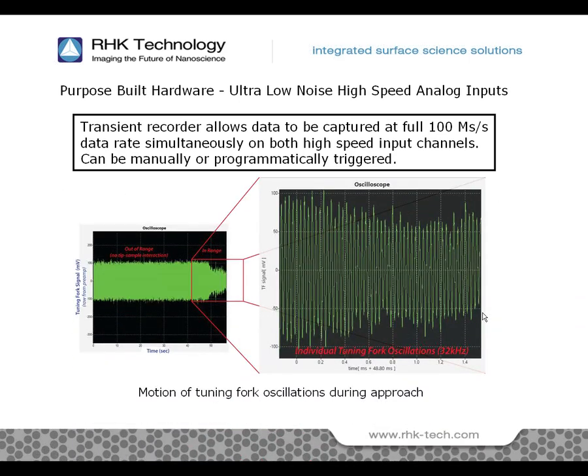If your input signal is from an oscillating probe, such as a cantilever or tuning fork, the graph will display the actual individual oscillations of the probe, and not just a low-frequency amplitude signal from your lock-in or PLL.